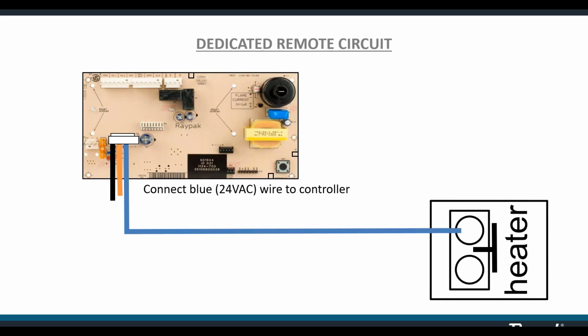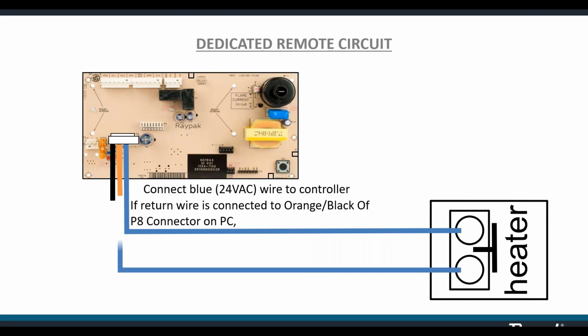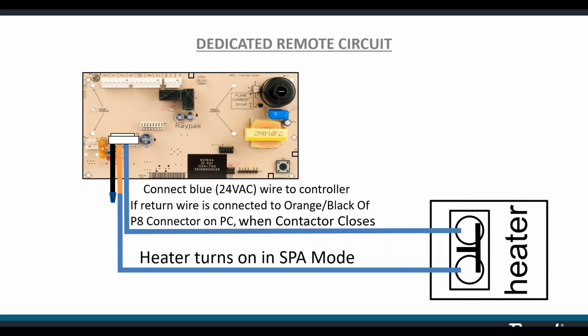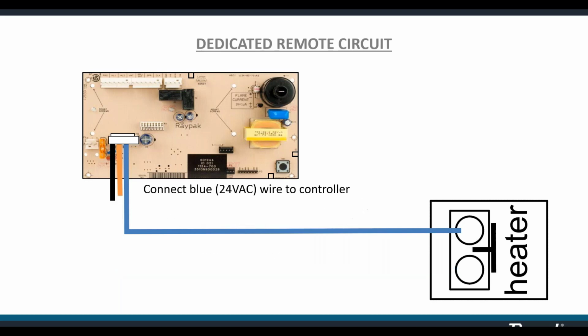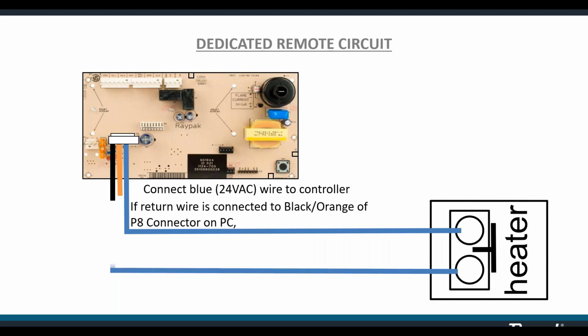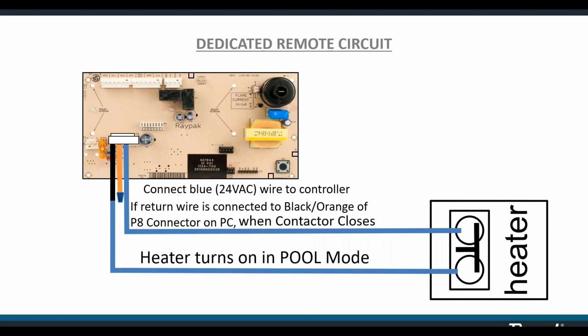Choose one of the other 2 remaining wires, it doesn't matter which, extend and attach that to the other side of the contactor. So if the return wire is connected to the orange-black at that P8 position on the board, when the contactor closes, the heater will turn on in spa mode, which means if you use the black-orange, when the contactor closes, the heater turns on in pool mode.